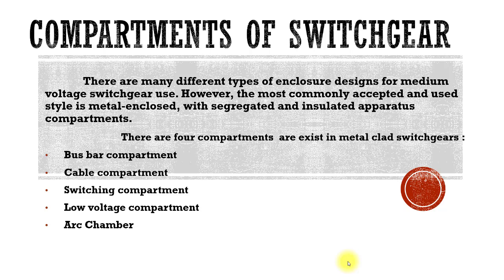Now we will see the different compartments that exist in the switchgear. There are many different types of enclosure designs for medium voltage switchgear in use. However, the most commonly accepted style is metal enclosed with segregated and insulated apparatus compartments. Most common designs have four compartments: the bus bar compartment, the cable compartment, the switching compartment, the low voltage compartment, and a less common arc chamber.